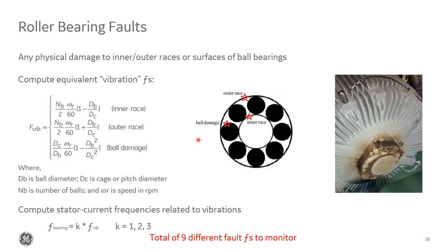So in the 869, we separate the ESA analysis into three main categories, where everything bucketed into these categories would have similar characteristics, and these types of fault would show up at similar fault frequencies. The first category is roller bearing faults. This would be any damage to the inner or outer race or the balls themselves. Specifically, this is applicable to ball bearings.